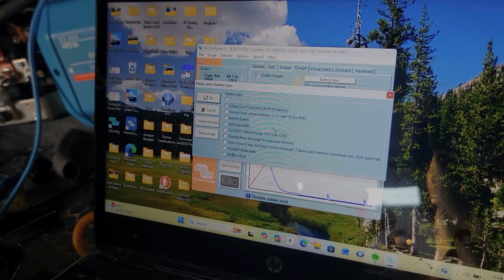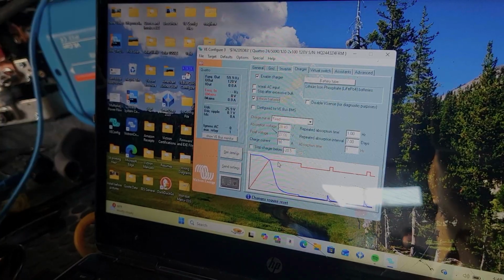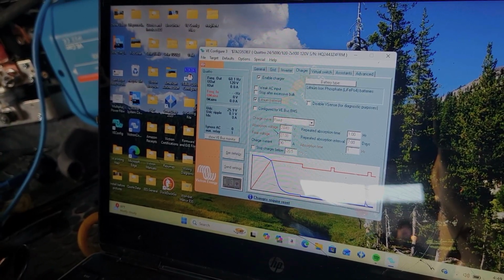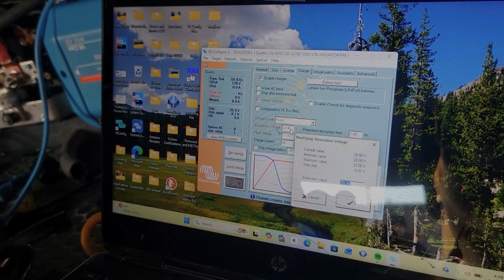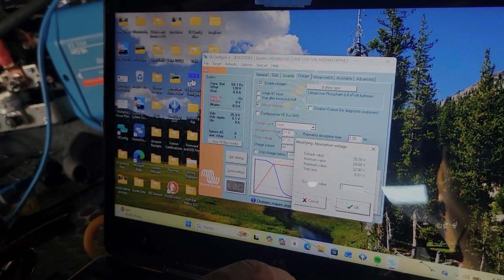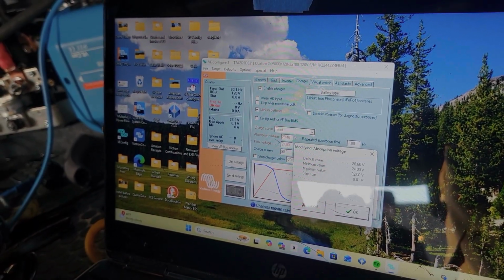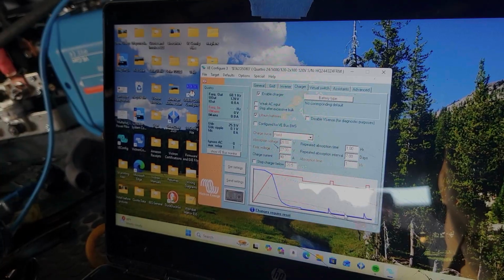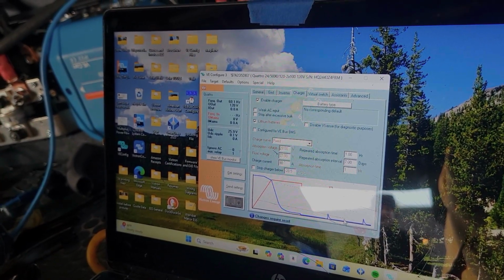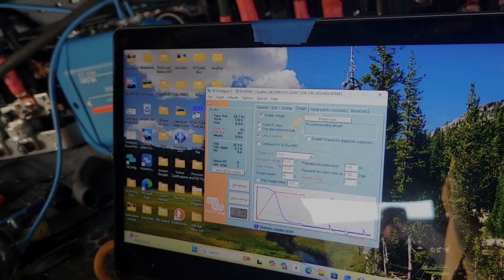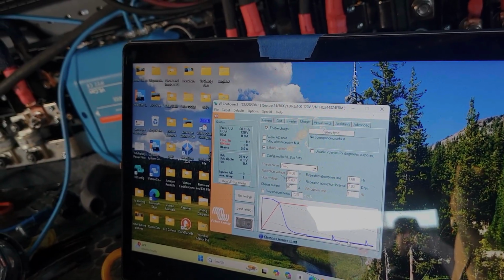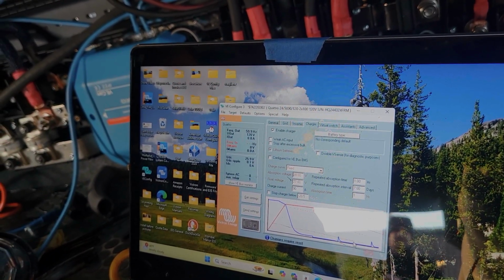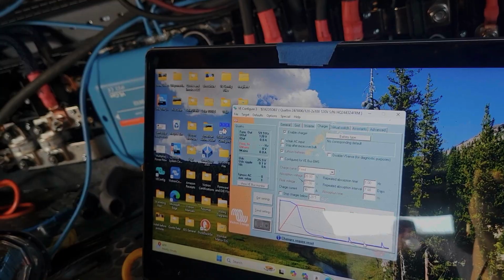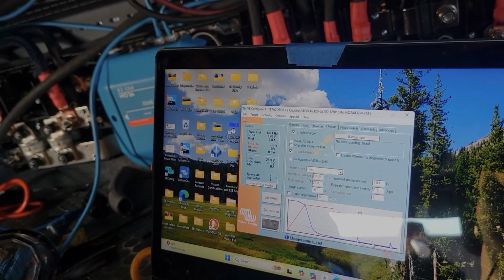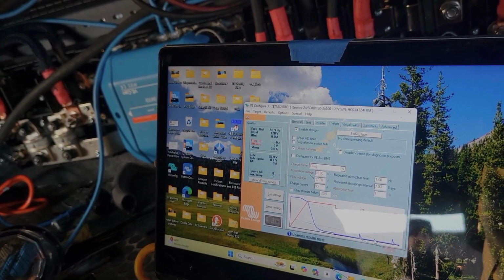We open the battery dialog, we select lithium iron phosphate and hit OK. Now, the absorption voltage is at 28.4. It's a little high for me. I like 28 to start. And the reason I like this is I like to slowly bring the batteries up to balance the cells, because we can't assume that these battery cells are balanced from the factory. But what we don't want to do is create spikes within those cells.